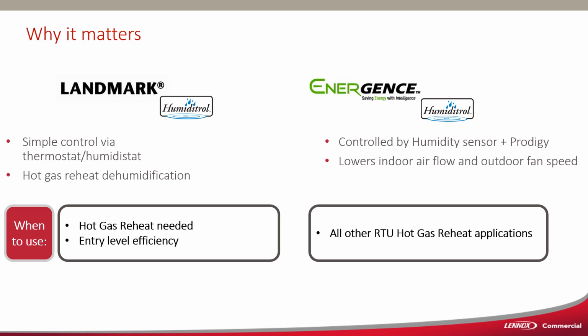We now have it. This is different than the hot gas reheat on the Energence package units because the Energence package unit has a Prodigy board, and the Prodigy board controls all of the functions and algorithms for the hot gas reheat performance, including how the hot gas reheat is staging, how the cooling is staging, the airflow CFM. We can lower the airflow to get a colder coil, increase dehumidification, and we can even slow down the outdoor condenser fan in order to get the hotter discharge gas temperatures.